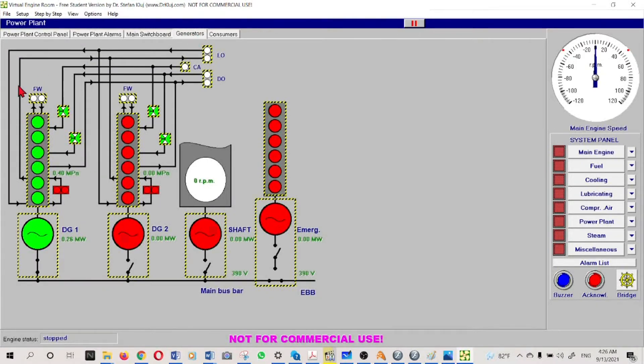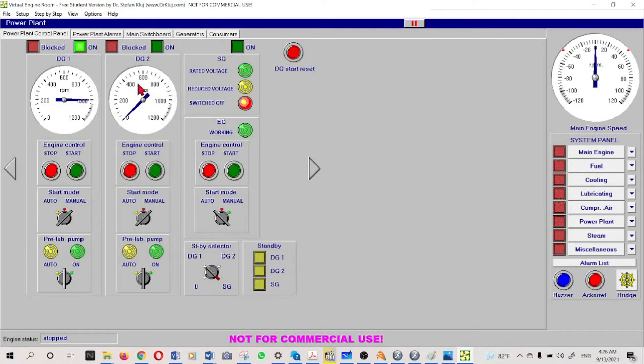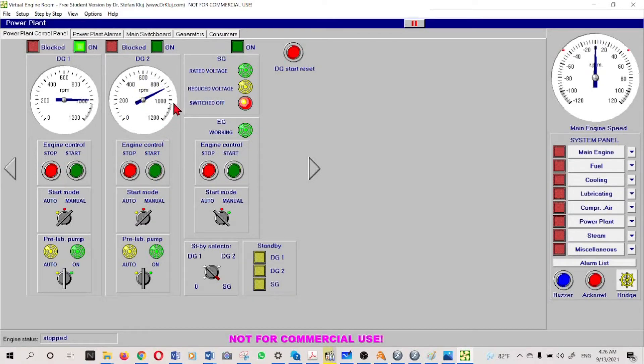The generator arrangement is a graphical representation. Number one generator - we can see all green, which means it is running and the breaker is connected to the bus bar and it is feeding load. The pre-lubricating pump is not running because the engine is running. Number two generator is not connected. Assuming everything is in standby, we are now going to start the generator.